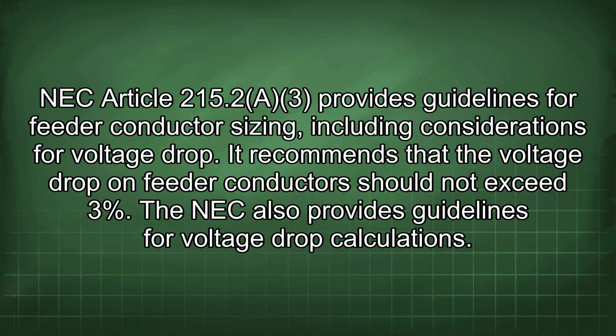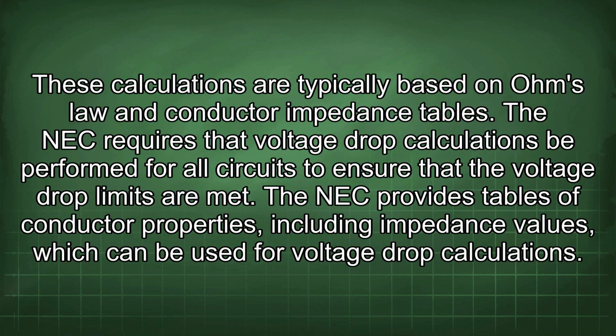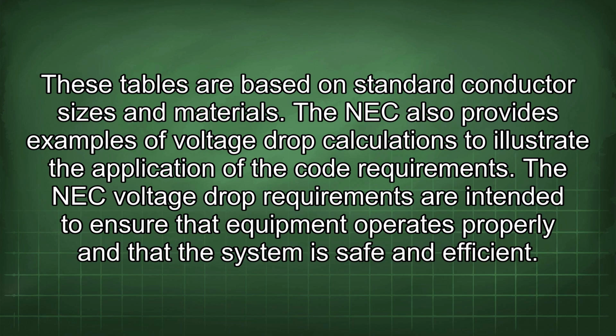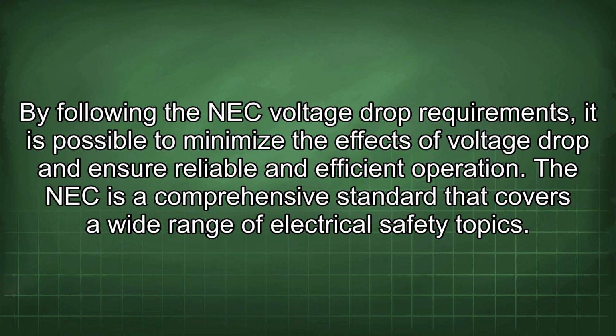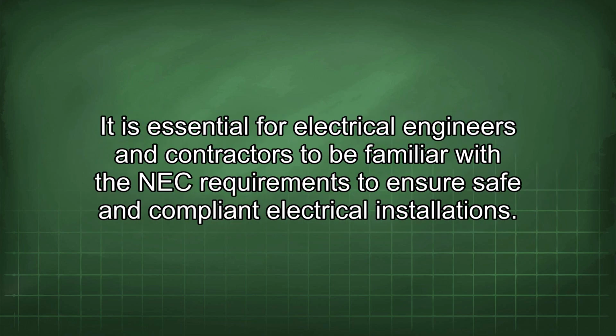The NEC also provides guidelines for voltage drop calculations. These calculations are typically based on Ohm's law and conductor impedance tables. The NEC requires that voltage drop calculations be performed for all circuits to ensure that the voltage drop limits are met. The NEC provides tables of conductor properties, including impedance values, which can be used for voltage drop calculations. These tables are based on standard conductor sizes and materials. The NEC also provides examples of voltage drop calculations to illustrate the application of the code requirements. The NEC voltage drop requirements are intended to ensure that equipment operates properly and that the system is safe and efficient. By following the NEC voltage drop requirements, it is possible to minimize the effects of voltage drop and ensure reliable and efficient operation. The NEC is a comprehensive standard that covers a wide range of electrical safety topics. It is essential for electrical engineers and contractors to be familiar with the NEC requirements to ensure safe and compliant electrical installations.